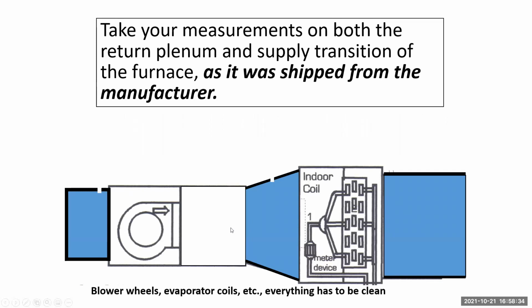Now, a lot of the newer techs out there don't know about static pressure, let alone how to check static pressure, where to check static pressure, any of that. This picture from left to right, left is your return into your blower through your furnace. That middle blue area is a transition into your evaporator and then out to your supply. If you look at your return and that transition, you'll see where the black line's notched out a little bit. That is where static is checked.